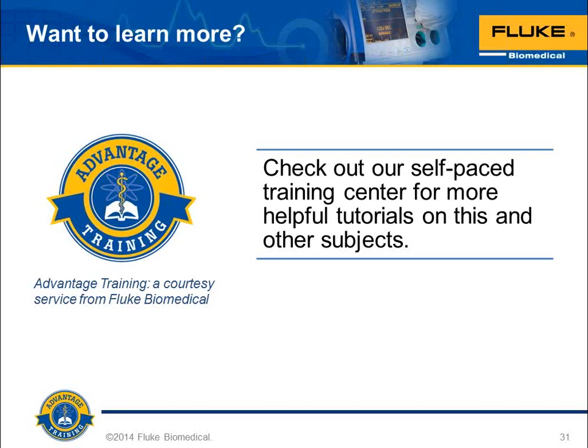And let's just take, for example, defibrillators and AEDs in particular, over 66,000 incidents just in the United States alone in the last 10 years. And that means that no matter what we're told about an AED, we're not doing the right test or the test frequently enough in order to capture the failures before they happen in clinical use. And so that tells us that we need to test and that we need to expand what we're looking at in what we're doing to test.